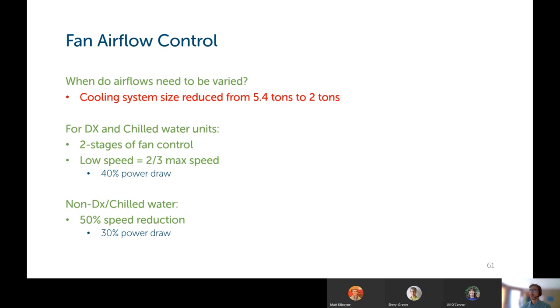Fan airflow control. So when do airflows need to be varied? The cooling system size where this is required has been reduced from 5.4 tons down to 2 tons. For direct expansion and chilled water units, you need to have 2 stages of fan control. The lowest speed must be at least 2/3 of the max speed, and must also draw 40% of the maximum power for those units. For any system that is non-direct expansion or chilled water, so anything else, you must have at least a 50% speed reduction, and at that reduced speed, it must be at most 30% power draw of full power.